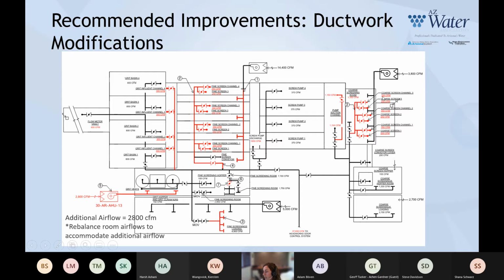So we added channel ducts in the coarse screen channels as well as at the coarse screening equipment, and we reduced the amount of foul air we drew from the coarse screen room. There was a single foul air duct in the screw pump influent, and we divided that flow in half, and we added a channel drop on the east end of this channel. We added a new supply header, but we didn't change any of the airflows coming from the supply air handling unit in the fine screen room, but we did add a supply air handling unit to disperse fresh air to the west end of the fine screen room.